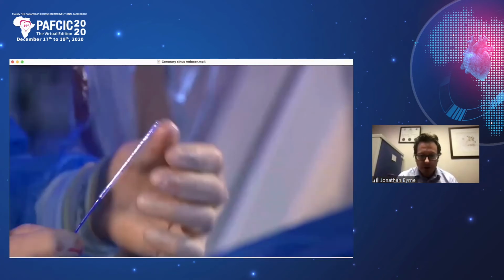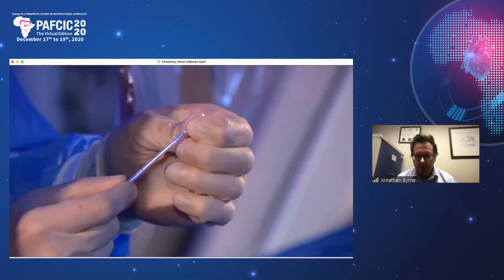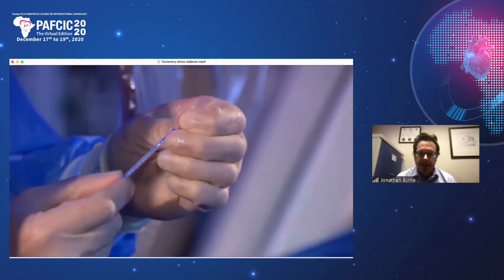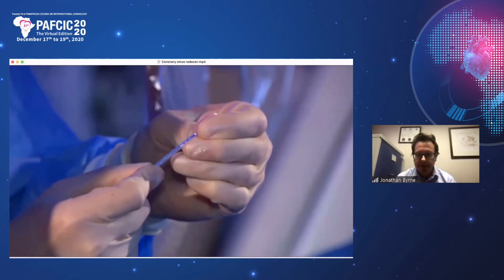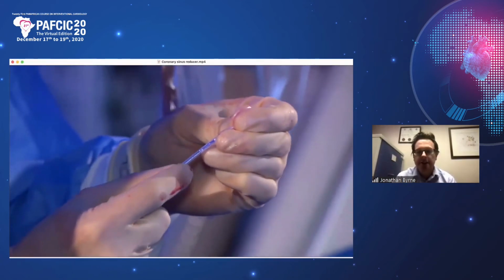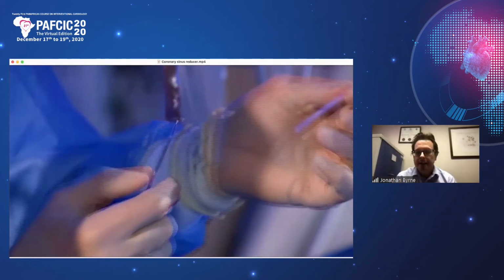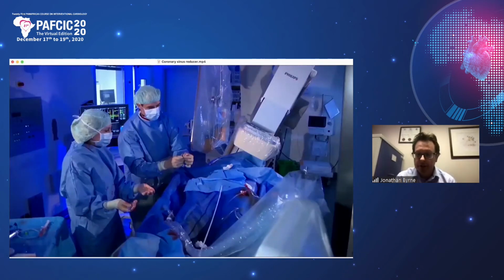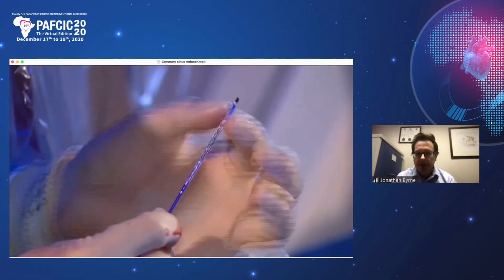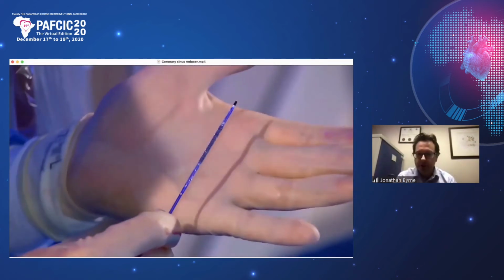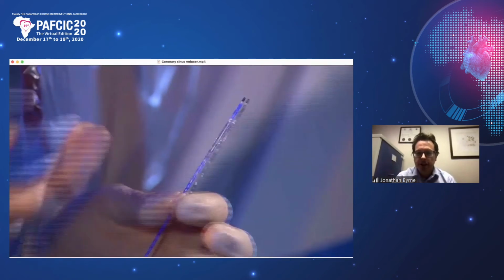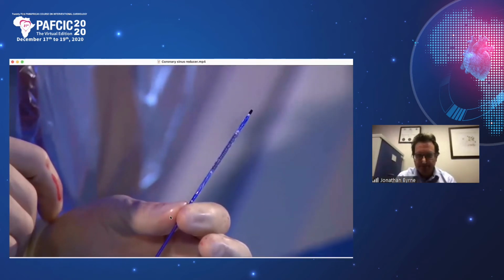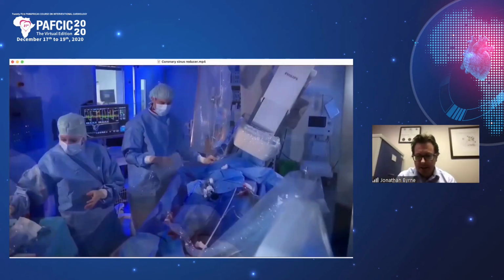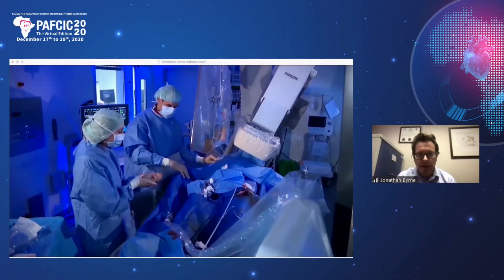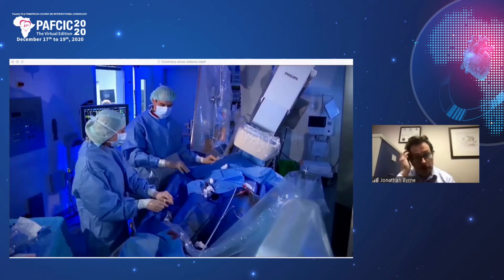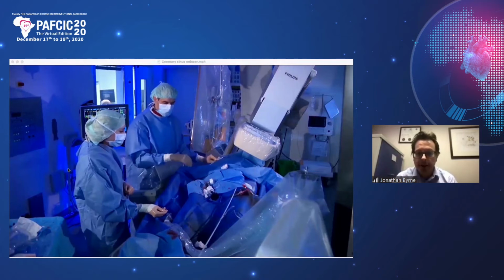It's important to check that it's crimped adequately onto the balloon. I think it's analogous to some of the first generation stent technologies, where the crimping process and the balloon are slightly first generation. So it's very, very easy for the device to come loose from the system itself, and very important that you are careful that it has not moved outside the markers before you put it in the patient.